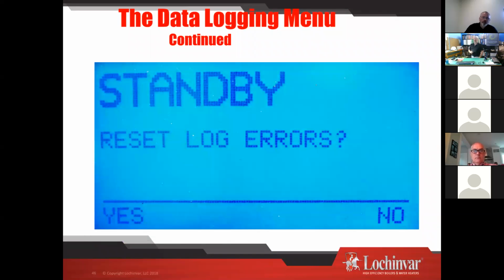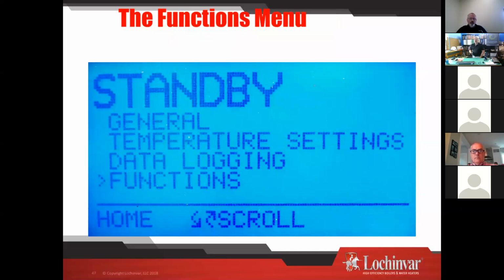All right, let's jump into data logging a little bit. Really, that's just to track and reset your log errors. So my recommendation to you is when you initially start your boiler up, if you're there and you're messing around with it and getting everything done, purging the air, purging the gas, whatever, reset your log errors before you leave. I'm notorious for it. If I come to your job and I'm working with the inspector and we test all the safeties, constantly I'm forgetting to do this before I leave. And then all of a sudden the next guy in goes, man, on one day they had 10 errors. What was it? This is a good way to just clear all that out of the memory so it's not there for the next guy.